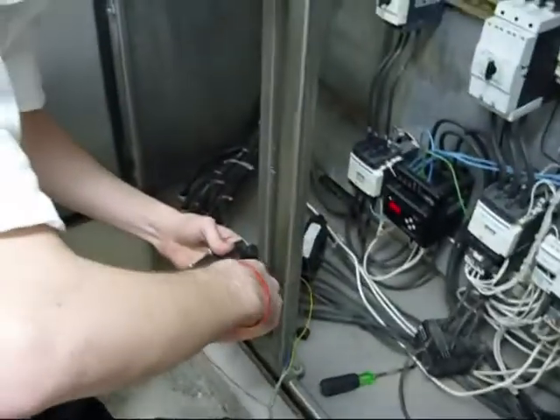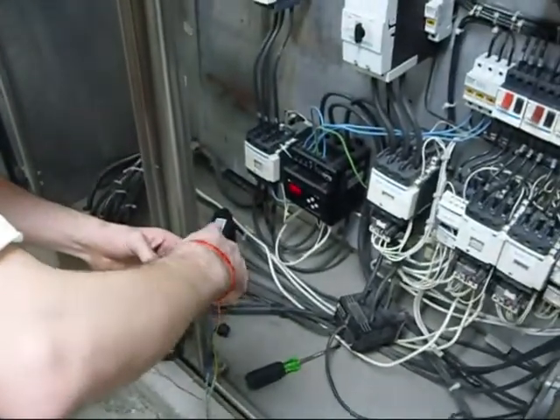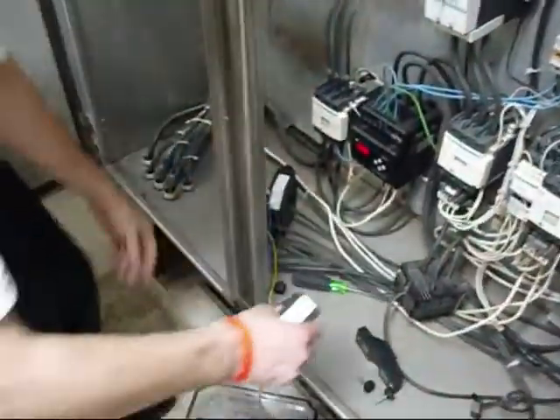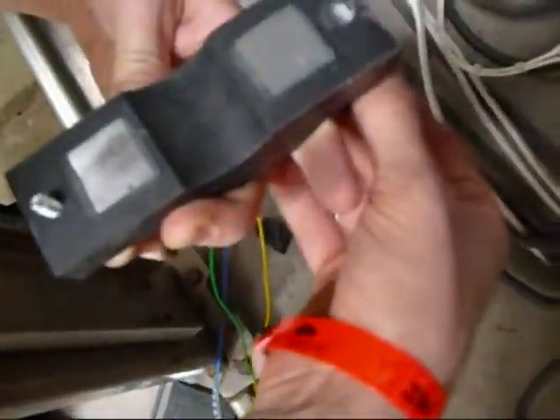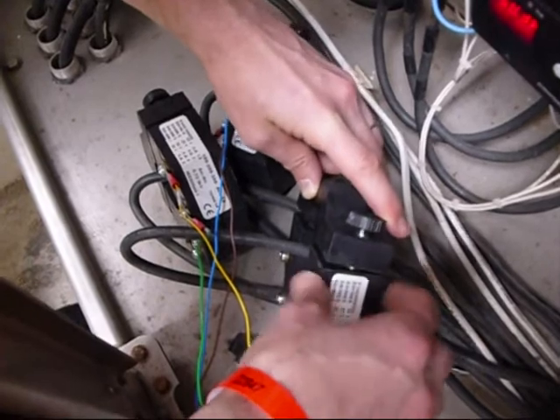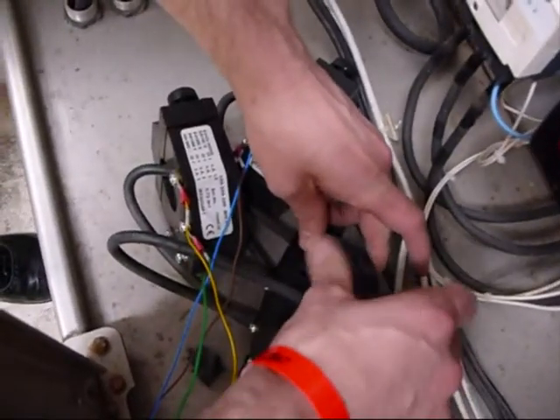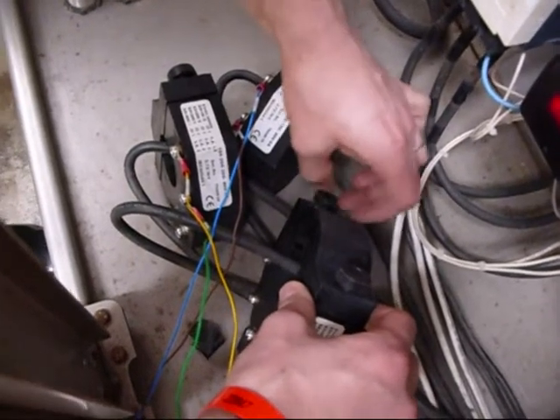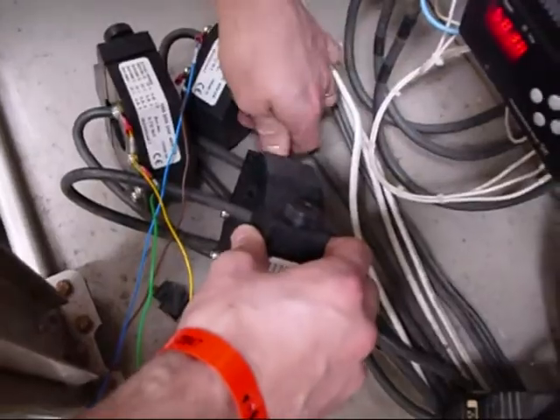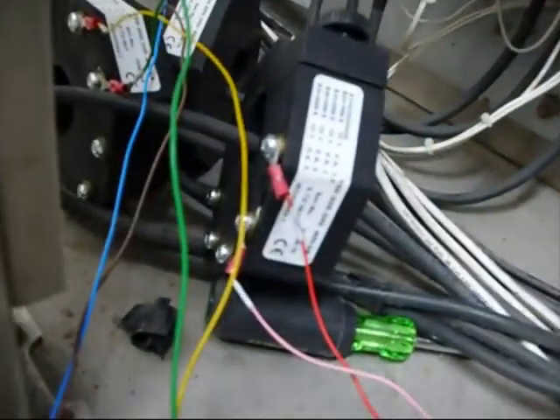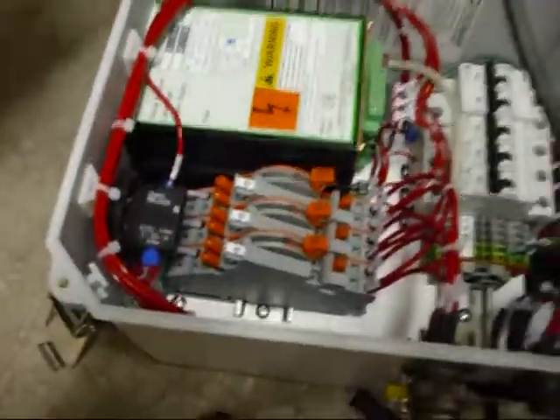So we're now going to install the 3rd CT, just to show you how it's done. These are split core CTs, so there's a section that comes off, detaches completely, which allows it to be slipped simply over the cable. And having slipped the CT over the cable, the cap then screws on with a couple of thumb screws. As you put the cap in place, you can feel the magnetic field pulsing through the CT. The cap's gently vibrating until it gets screwed tight down when it feels smooth. And just to repeat the point, these two cables, the outputs from the CT, follow down this cable here and into the connection on the side of the unit, come into these shorting links here.